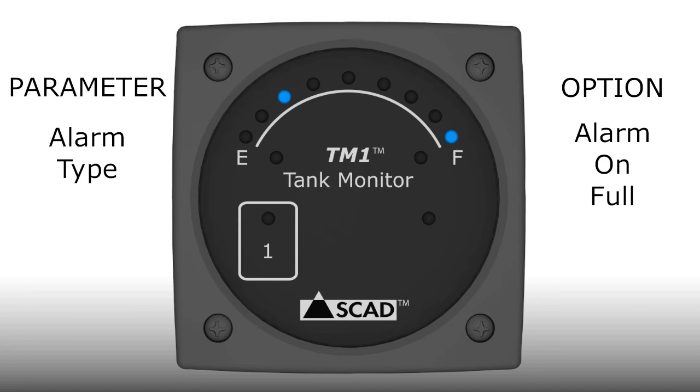The monitor will proceed to the final parameter, which is the alarm type, indicated by the 1 light. There are three options. The first option, indicated by the F light, is alarm on full, meaning the alert light will turn on when the level is just over 7/8 full. This is the default option. The next option is indicated by the E light, which represents alarm on empty — the alert light will turn on when the level is just under 1/8 of a tank. The next option is no alarm, indicated by the half light.